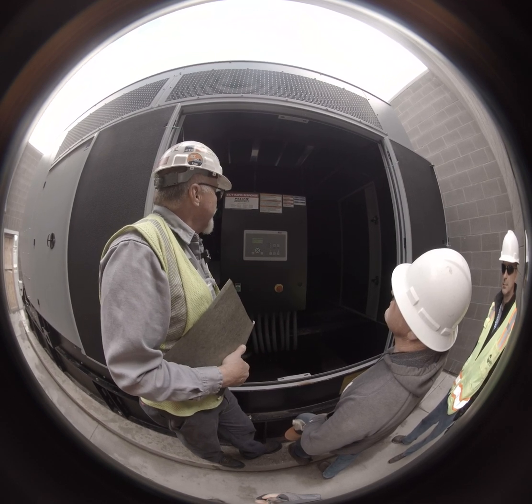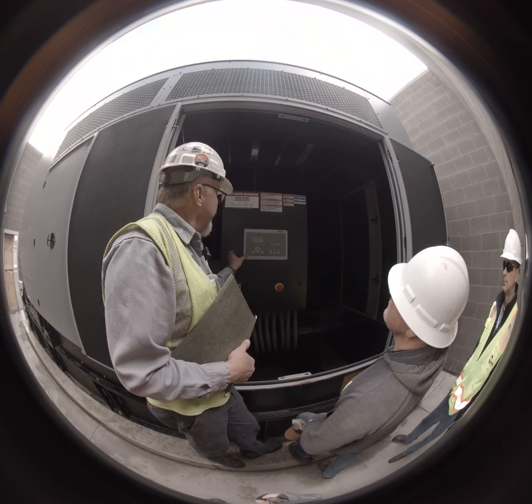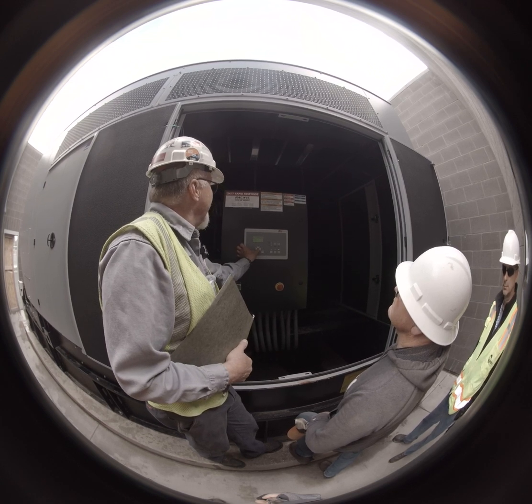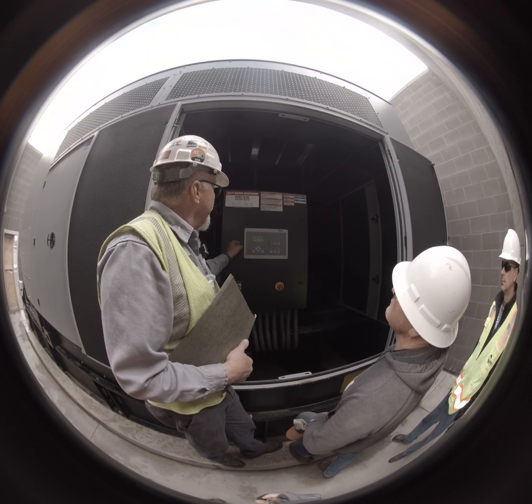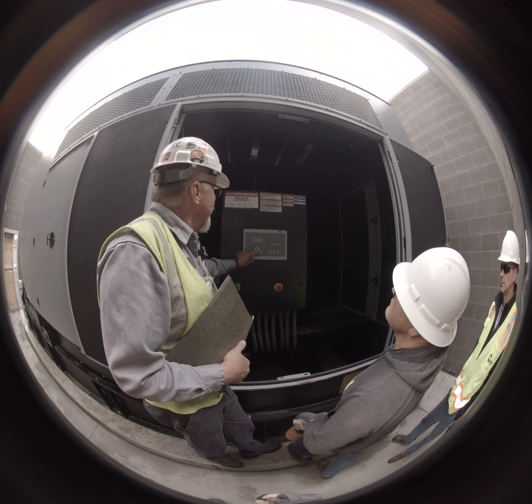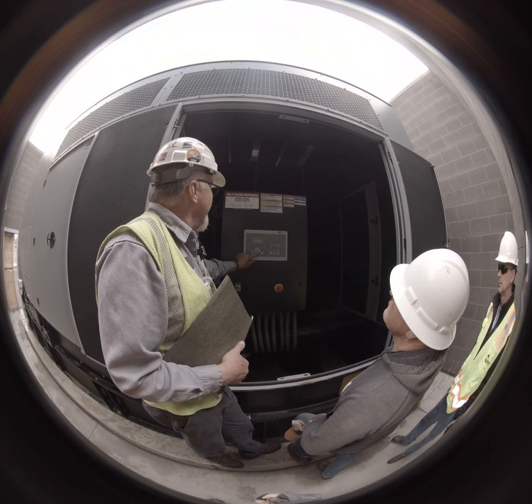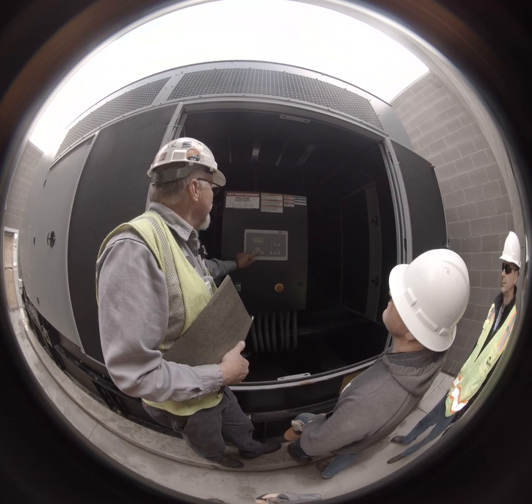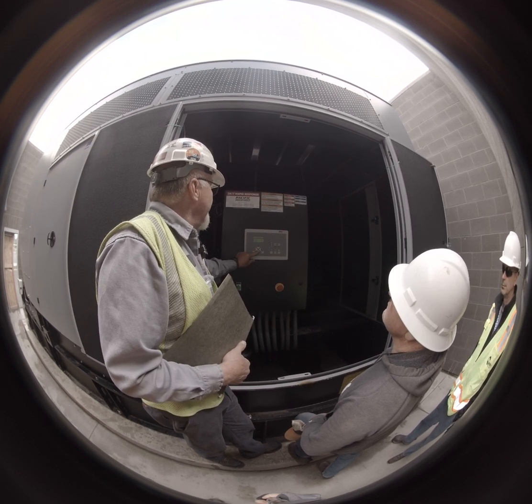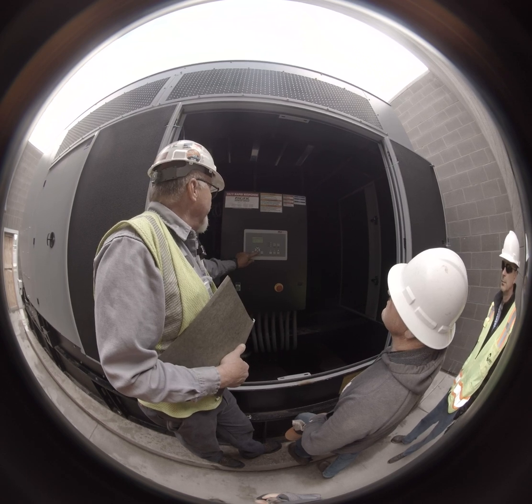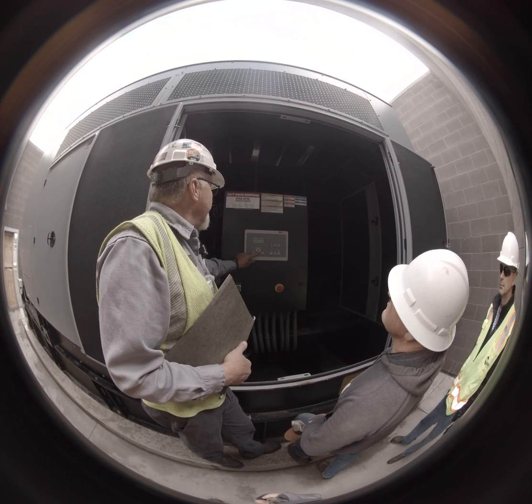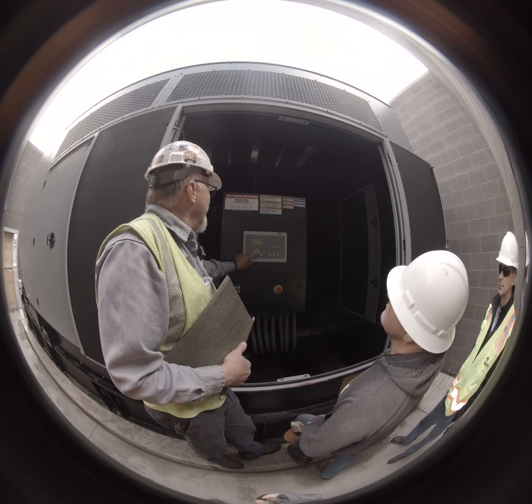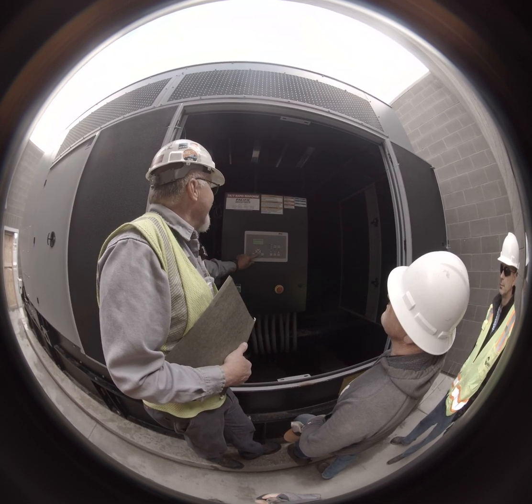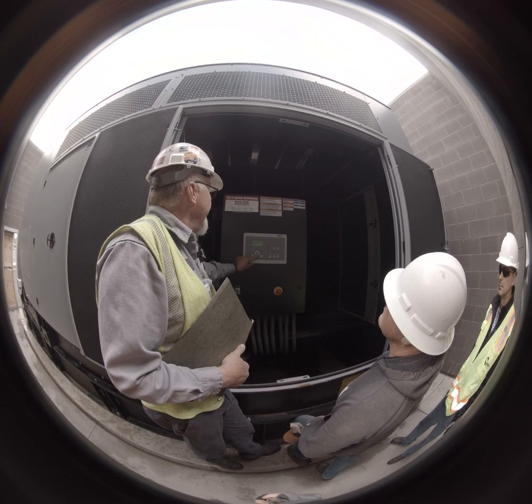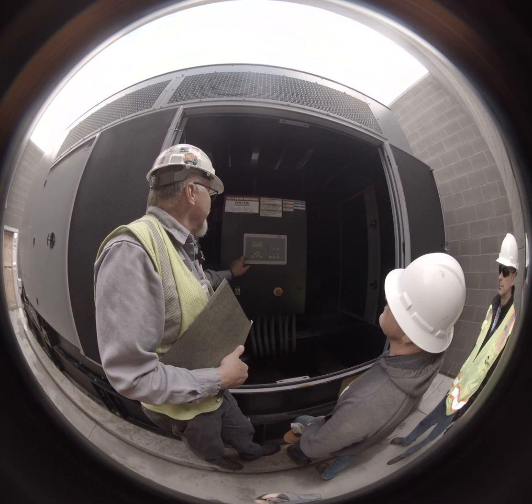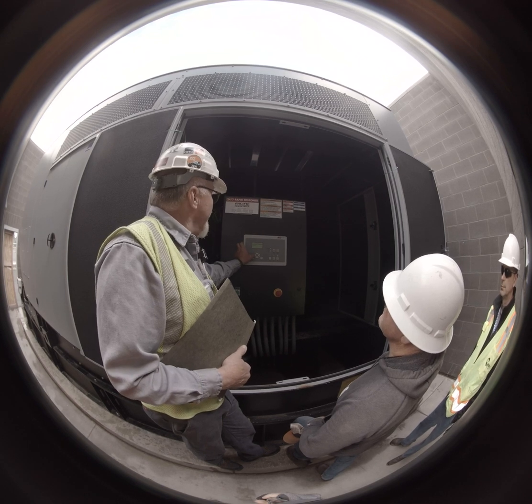Next one is your generator parameters, which is your voltages, amperages, and such. So it's three-phase Y, and all your voltages will come up when we run the engine. Voltage is line to line, voltage is line to neutral, frequency, amperage on each phase. If you were reading a bus, which we do not on this one, you can see what the bus is doing. It does a lot. Vector shift, rate of change. So. Then you go back one more.